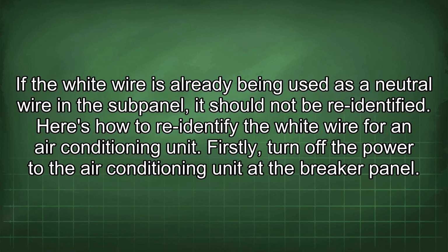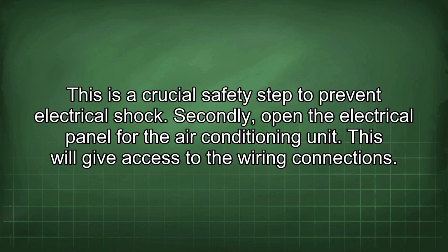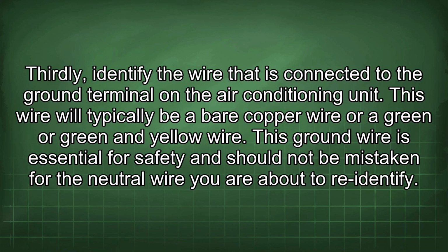Firstly, turn off the power to the air conditioning unit at the breaker panel. This is a crucial safety step to prevent electrical shock. Secondly, open the electrical panel for the air conditioning unit. This will give access to the wiring connections. Thirdly, identify the wire that is connected to the ground terminal on the air conditioning unit. This wire will typically be a bare copper wire or a green and yellow wire. This ground wire is essential for safety and should not be mistaken for the neutral wire you are about to re-identify.